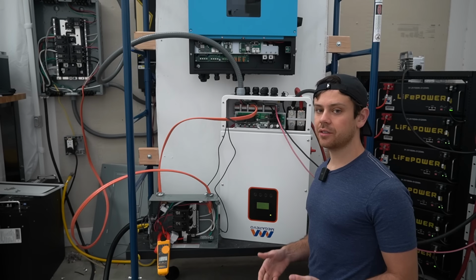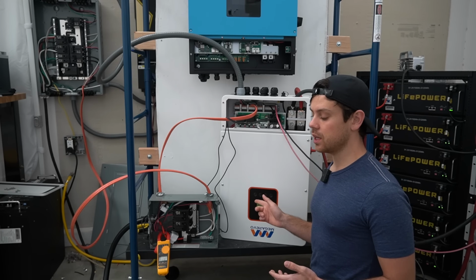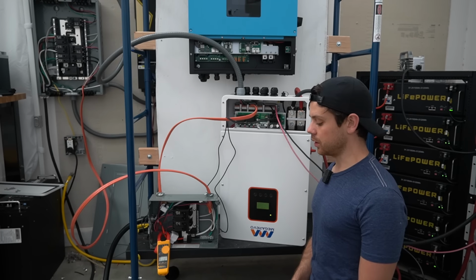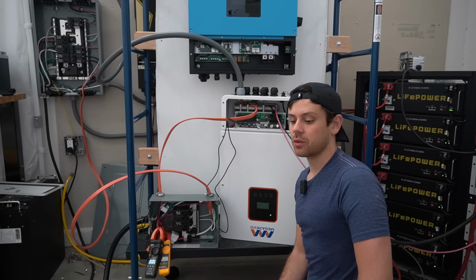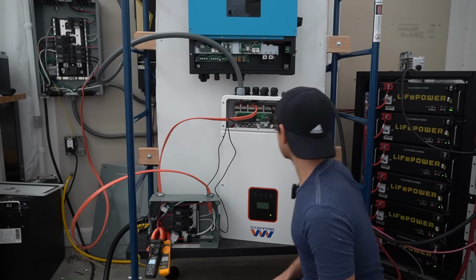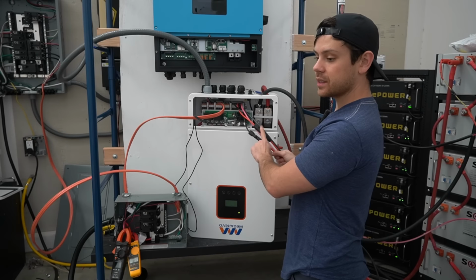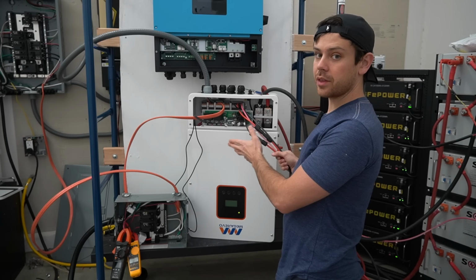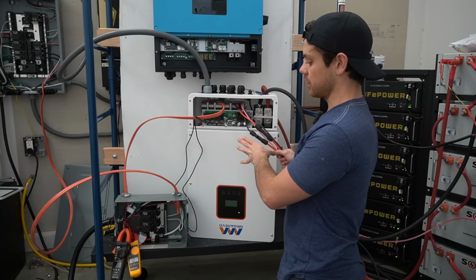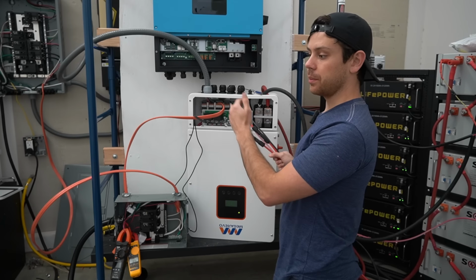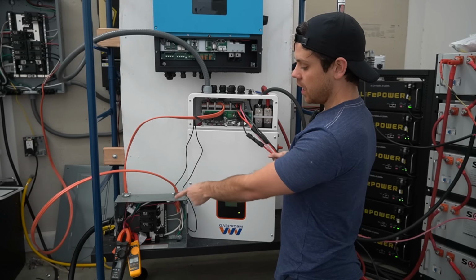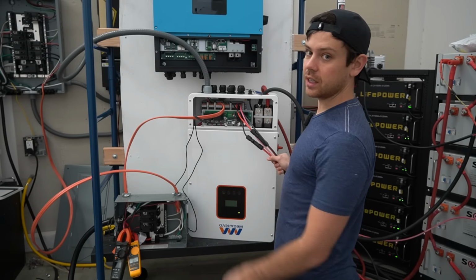Now we do not have enough solar power to actually run this load yet, so we're gonna wait until the sun comes up. Maybe we should connect a larger array. I could do that in a few minutes actually. Now we have a second array, so we have a total of 3,000 watts connected to this inverter. So we're gonna wait until the sun comes up all the way and they actually have sunshine, and then we should have current actually feeding these loads.